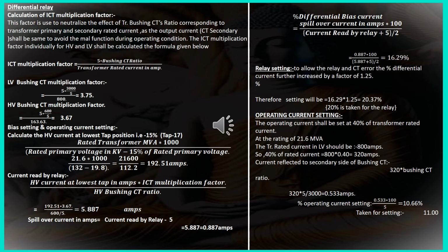I have shown you the setting for the primary side and transformer side LV. Setting you have to decide for any changes. Initially during commissioning the company will give, but you have to give them the data, how to set, what is the limit, your sectional area that it will protect.